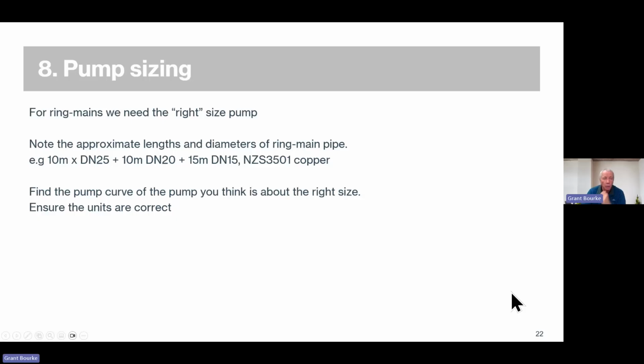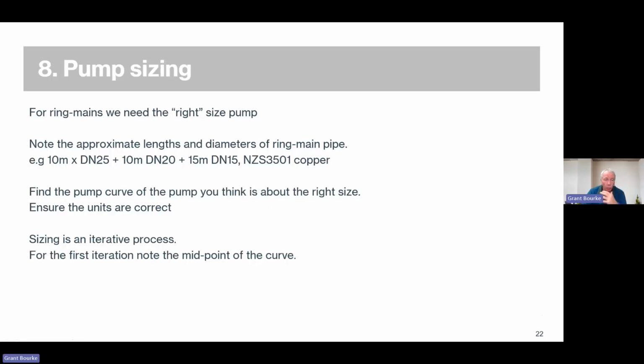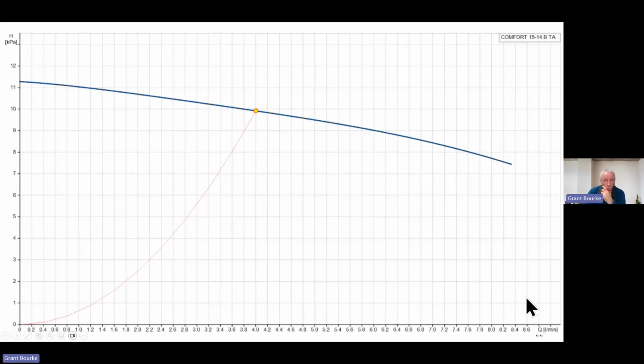So the first step you want to do is go and find the pump that you think's about the right size, and make sure that you're looking at the correct units. The pumps are litres a second, litres a minute, cubic metres an hour, metres a head, kilopascals. So make sure that what you're looking at is the units that you think you're looking at. If you're not looking at the right units, it should become pretty obvious as you go through. So sizing this pump takes a couple of iterations. And so what we want to do is get that pump curve for the pump we think we might want to use and have a look at the midpoint of that curve.